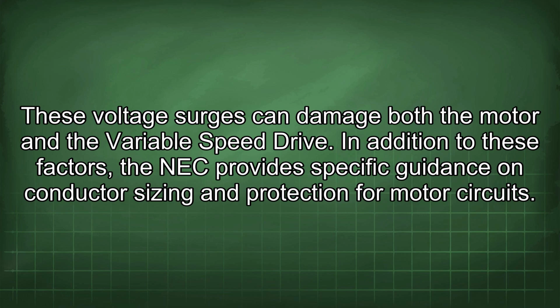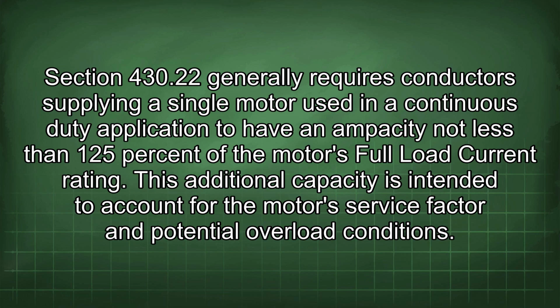In addition to these factors, the NEC provides specific guidance on conductor sizing and protection for motor circuits. Section 430.22 generally requires conductors supplying a single motor used in a continuous duty application to have an ampacity not less than 125% of the motor's full load current rating. This additional capacity is intended to account for the motor service factor and potential overload conditions.